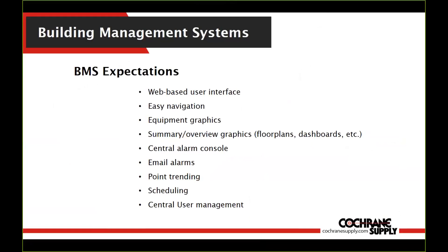In a traditional BMS, you expect a web-based user interface, some navigation, equipment graphics for your plant, your terminal equipment like your RTUs and your VAVs, maybe some overview graphics like floor plans, dashboards, maybe some grids or reports, a centralized alarm console so you can get visibility into system-wide alarms, email alarming so that you can get notifications when you're not on site, whether that be through email or SMS, trending so you can look at historical data for all your points, scheduling, and a centralized user management.